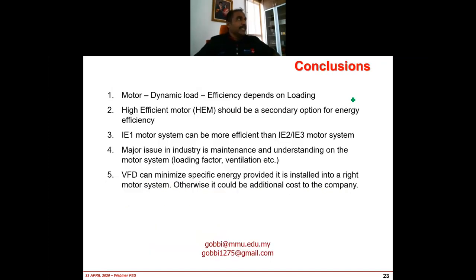Okay, as a conclusion. As I mentioned to you, when it comes to motors, it is a dynamic load. We have to understand the efficiency depends on the loading. And therefore, a high efficiency motor should be a secondary option. Don't blindly change to high efficiency motors because it may not give you any savings. So you have to look at the loading condition first. Make sure that you optimize the current system. Make sure that it runs at 70% or 80% load before you think about going for high efficiency motors.